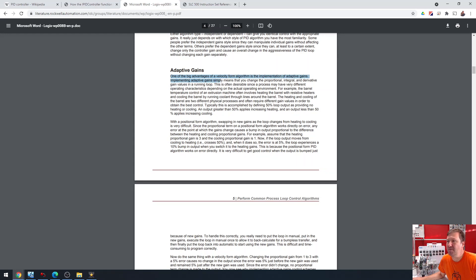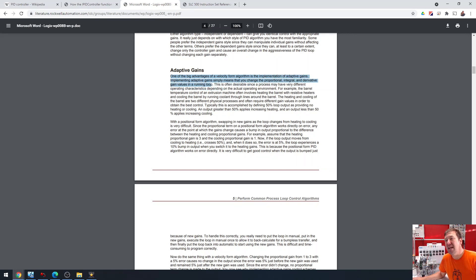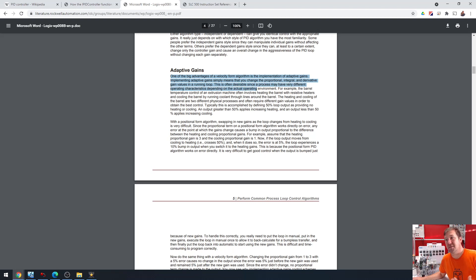Implementing adaptive gains simply means that you change the proportional, integral, and derivative gains in a running loop. This is often desirable, since a process may have many different operating characteristics depending on the operating environment.